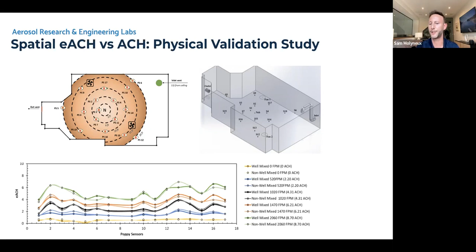What we're really doing is a fairly simple procedure in rooms. It comprises defining a zone in a building, which we think of a little differently in some cases than an air control zone. In ventilation, we think of our zones as logical airspaces with some consistency in how the air is treated. Ideally you'd have some control mechanisms within that zone definition. We do a triplicate rapid air test, using three different sensors and a single release from one or more diffuser devices, depending on the level of background particles in the space.